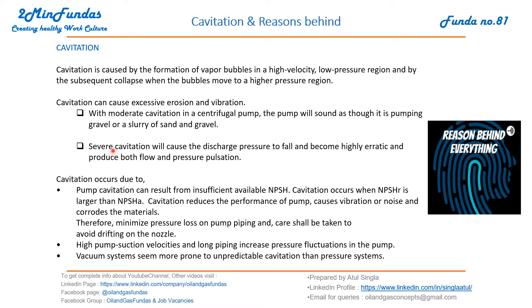If the level of cavitation is severe, it will cause the discharge pressure to fall and become erratic — highly erratic — and produce both flow and pressure pulsation. If the level of cavitation is very high, then it can cause all these problems.